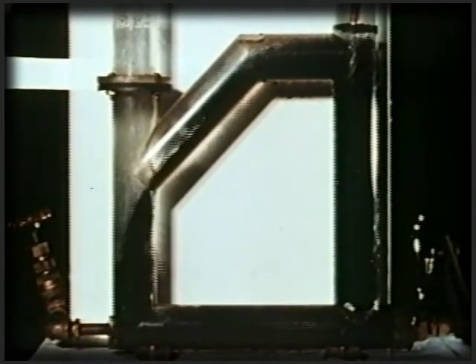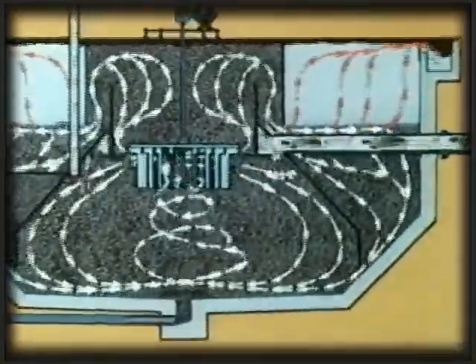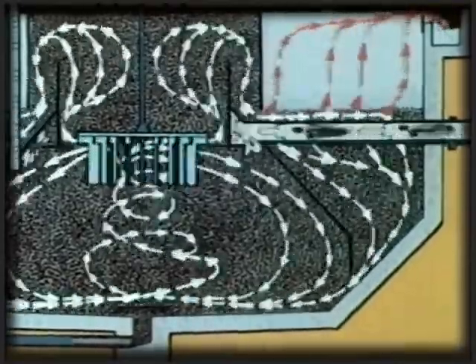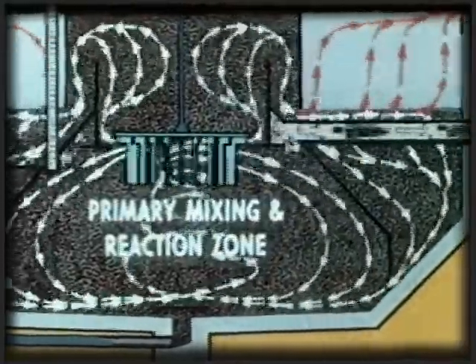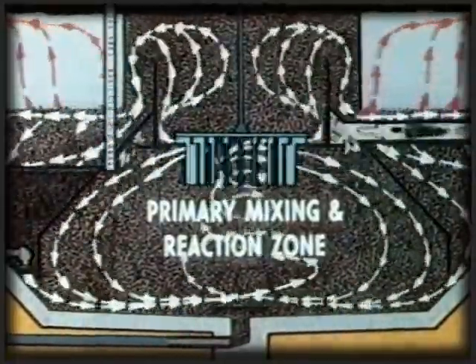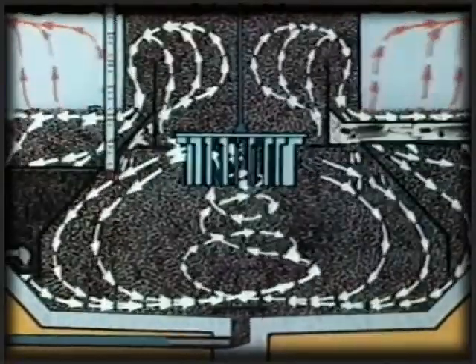In effect, this model is a cross-section of the action which takes place in the Accelator and illustrates the principle on which it is based. An animated cross-section of an Accelator shows how it is applied. Raw water enters at the top of the primary mixing and reaction zone, where it is quickly assimilated into a circulating mass of slurry. Meanwhile, a steady stream of carefully balanced chemicals enters through the vertical tube on the left. This ensures quick coagulation.